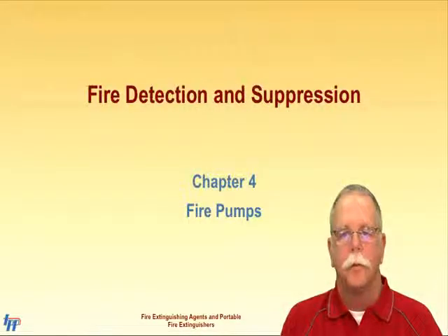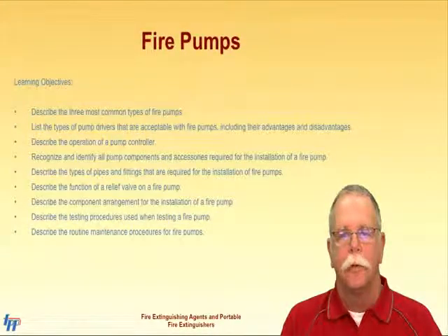The main function of a fire pump is to increase the pressure of water that flows through it. Common types of fire pumps include split case pumps and vertical shaft turbine pumps. The engines or motors used to turn the pumps are called pump drivers. Drivers commonly are powered electrically, by diesel engines, or by steam turbines. Pump controllers, which control pump operation, vary according to the type of pump driver.